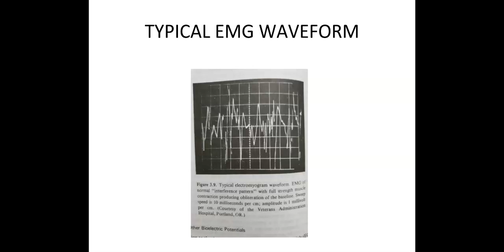The EMG machine or electromyograph looks like this. Features of EMG machine. Surface or needle electrodes are used. Both unipolar or bipolar measurements are used. The amplifier for EMG measurements must have high gain, high input impedance and a differential input with good common mode rejection ratio or CMRR. However, the EMG amplifier must accommodate the higher frequency band.